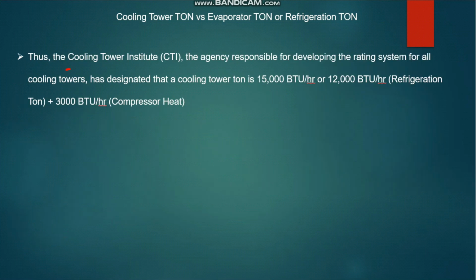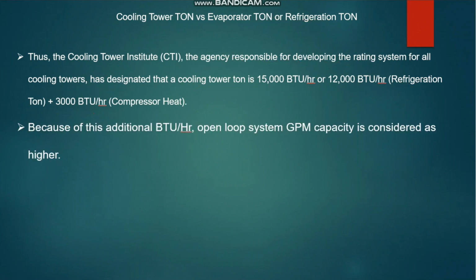That is the reason the Cooling Tower Institute, or CTI, the agency responsible for developing the rating system for all cooling towers, has designated that the cooling tower ton is 15,000 BTU per hour: 12,000 BTU per hour, the refrigeration ton or chiller ton, plus 3,000 BTU per hour because of the compressor heat. So in total it is 15,000 BTU per hour for the cooling tower ton, and for the evaporator or refrigeration ton it is 12,000 BTU per hour. Because of this additional BTU per hour from the compressor heat, with the open loop system, that means chiller to cooling tower, GPM capacity is considered higher compared with the closed loop system.